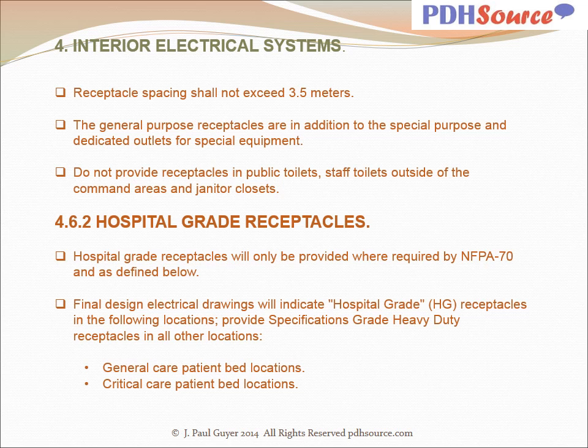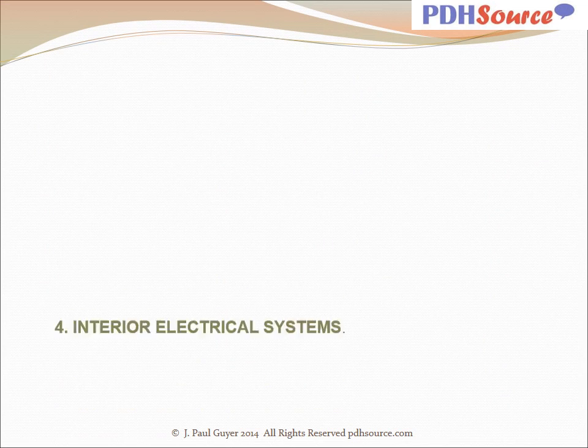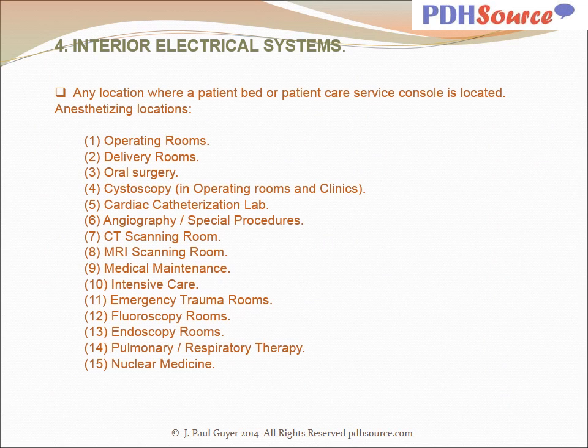Hospital grade receptacles will only be provided where required by NFPA 70 and as defined below. Final design electrical drawings will indicate hospital grade receptacles in the following locations. Provide specification grade heavy duty receptacles in all other locations. General care patient bed locations, critical care patient bed locations. Any location where a patient bed or patient care service console is located.